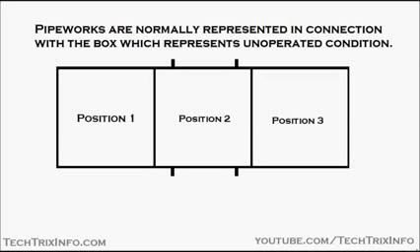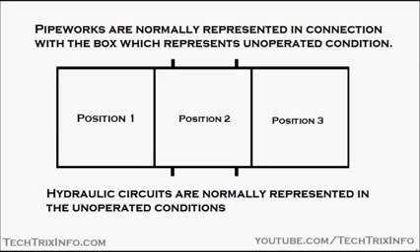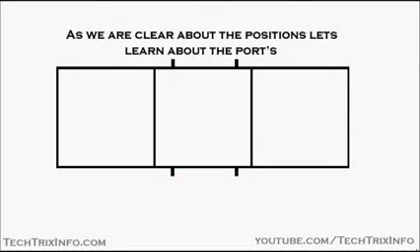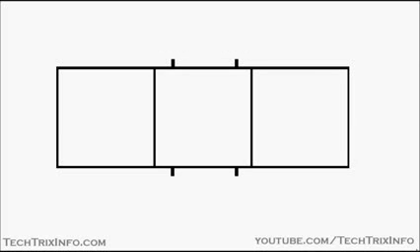The pipework is normally represented in connection with the box which represents the unoperated condition. Here, the unoperated condition is position two, where all the ports are blocked. Hydraulic circuits are normally represented in the unoperated position, which is position two, and those are the pipework connections.